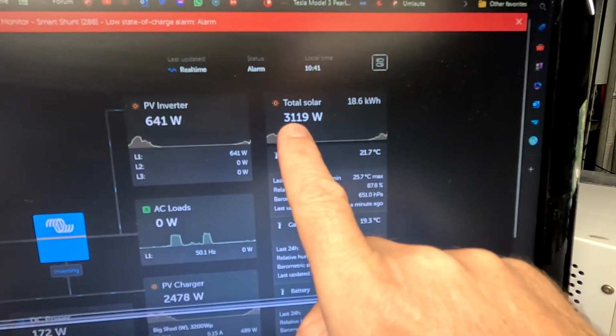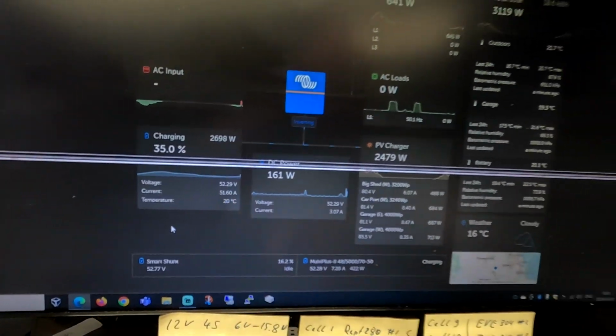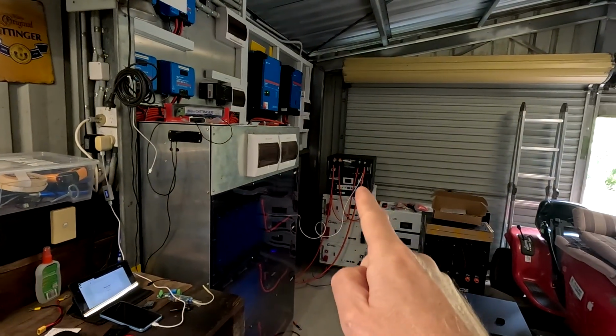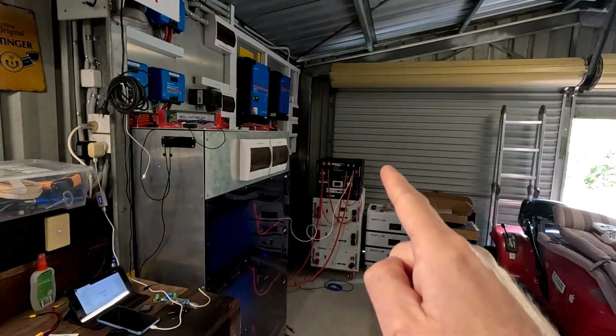Now we are getting 3.2 kilowatts from the solar system, and we are charging these 2 batteries with 51.6 amps. These are only 100 ampere hour batteries, so 50 amps going in, or 25 each. I have set the maximum charge current to 50 amps, so 100 amp maximum charge current into these batteries.